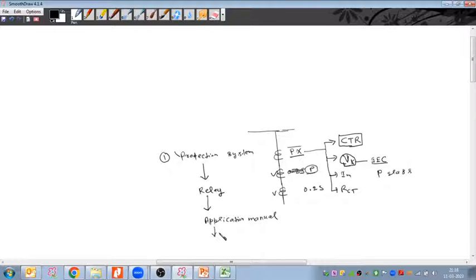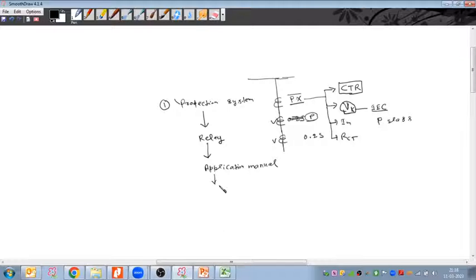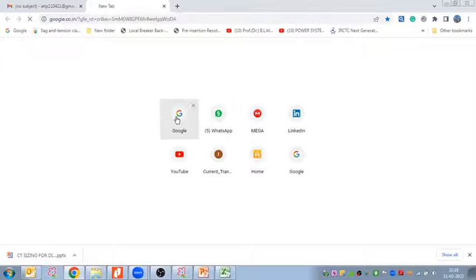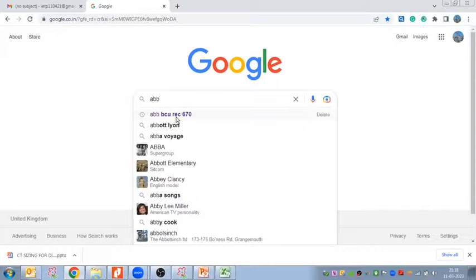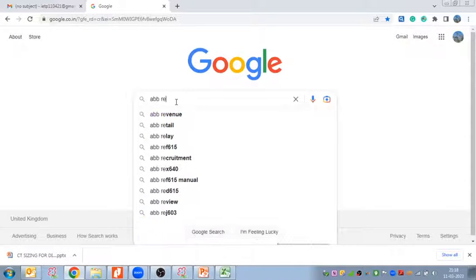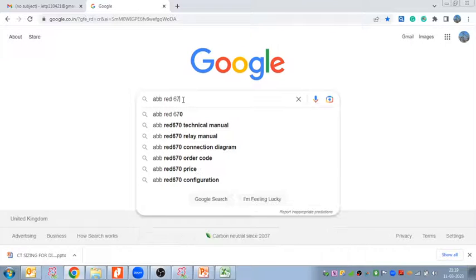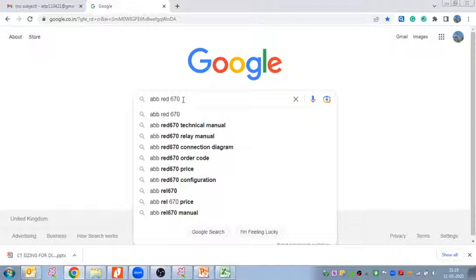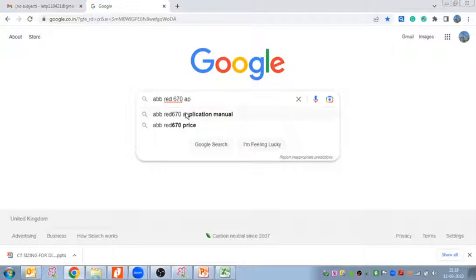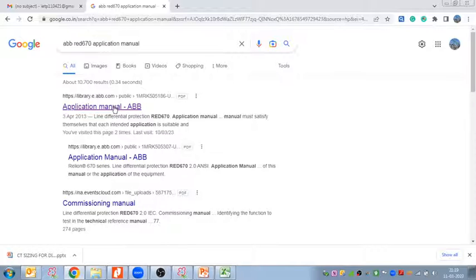So no need to read all 600 or 700 pages. Only go directly to the CT requirement page and note down the CT requirement formula. I think yesterday we downloaded the manual. I think we downloaded the ABB RED manual. The technical manual is also available, but no need to select it, no connection diagram, nothing. Just type application manual. Application manual. So this is the link for the ABB library.